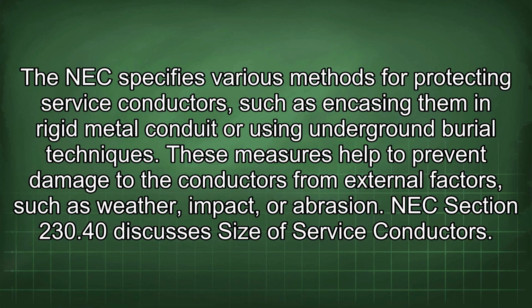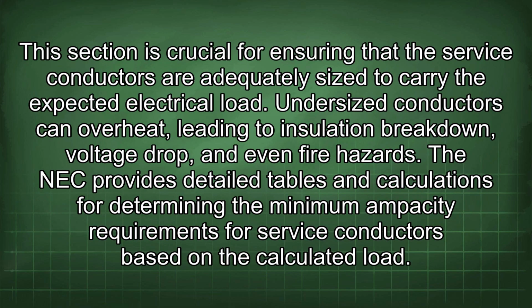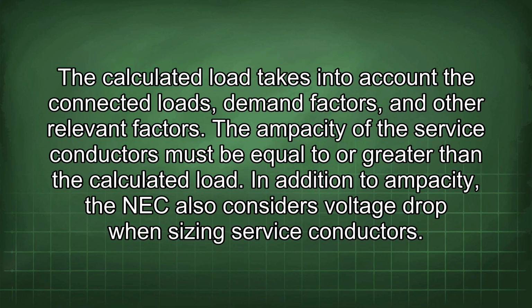NEC section 230.40 discusses size of service conductors. This section is crucial for ensuring that the service conductors are adequately sized to carry the expected electrical load. Undersized conductors can overheat, leading to insulation breakdown, voltage drop, and even fire hazards. The NEC provides detailed tables and calculations for determining the minimum ampacity requirements for service conductors based on the calculated load. The calculated load takes into account the connected loads, demand factors, and other relevant factors. The ampacity of the service conductors must be equal to or greater than the calculated load.